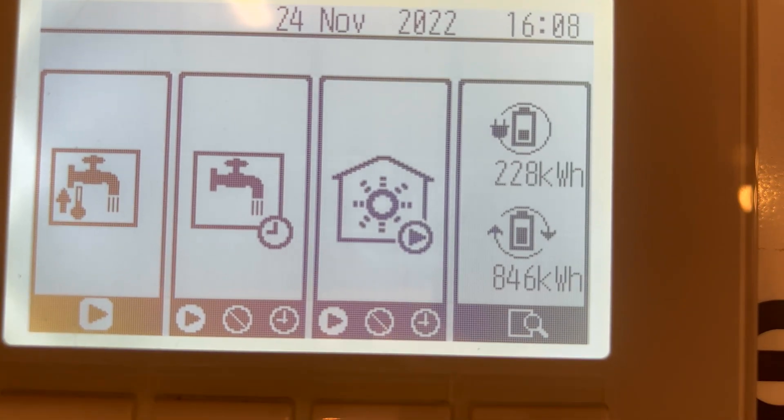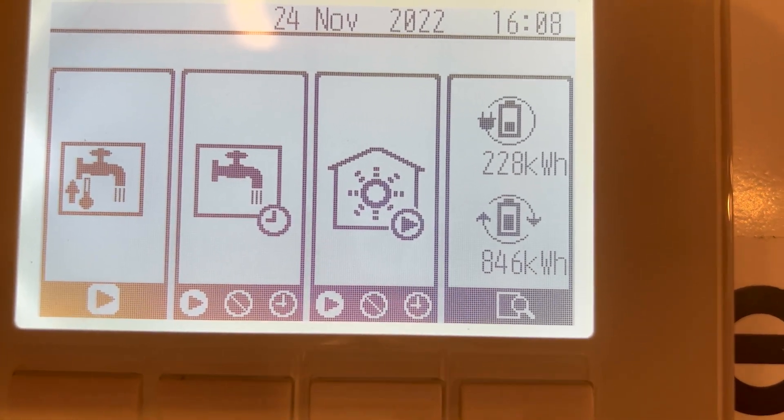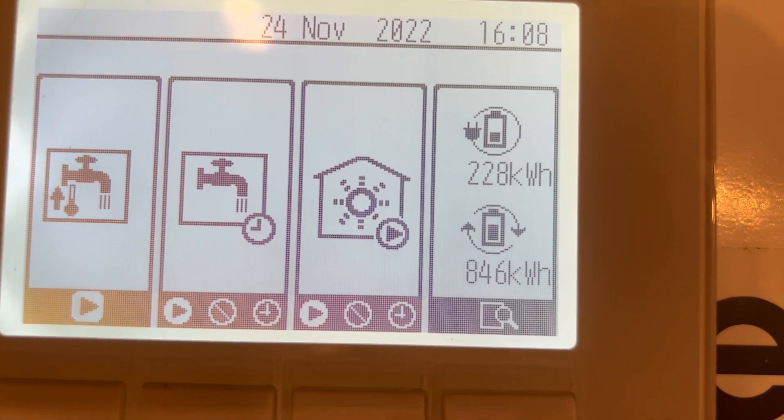It's 228 kilowatt hours in — that's electrical power — and 846 kilowatt hours out. So 228 kilowatt hours of electric in generates 846 kilowatt hours of heat out, and that's for heating hot water and for heating the house.